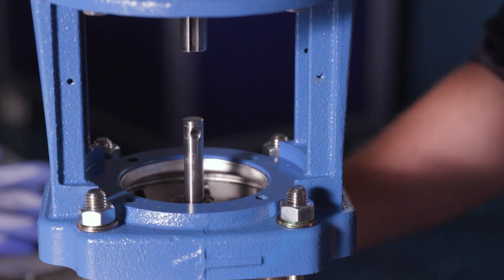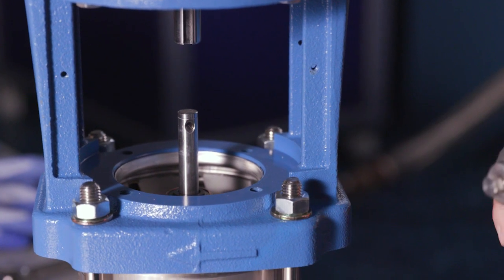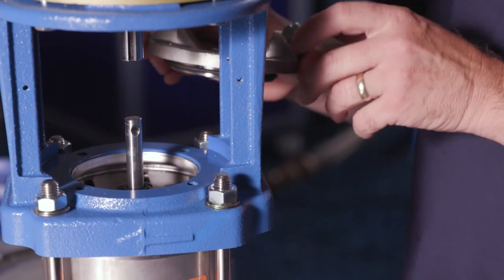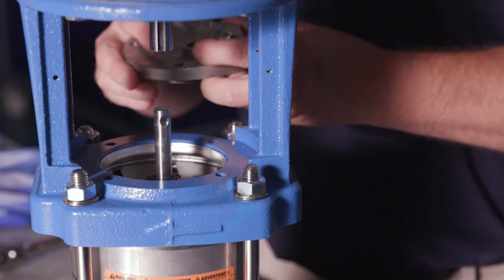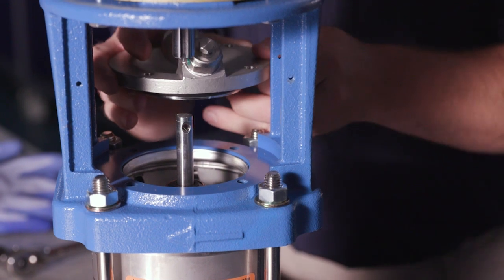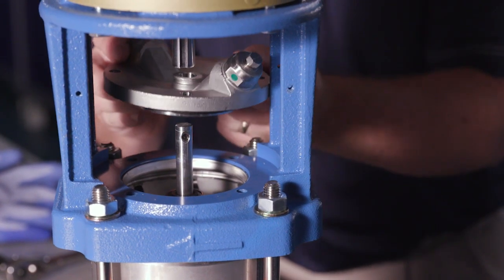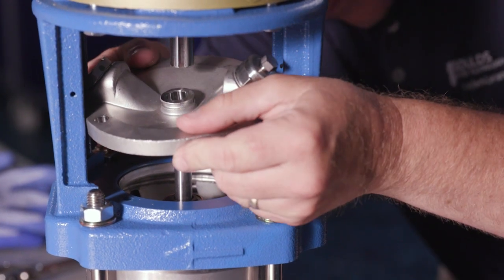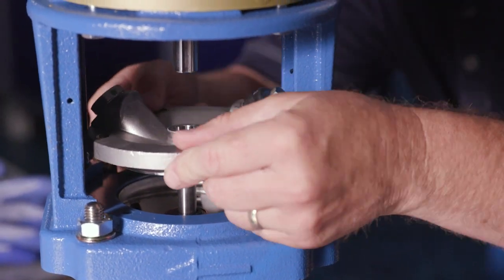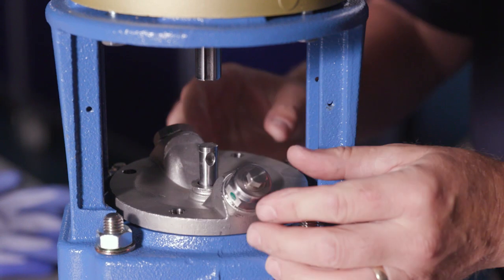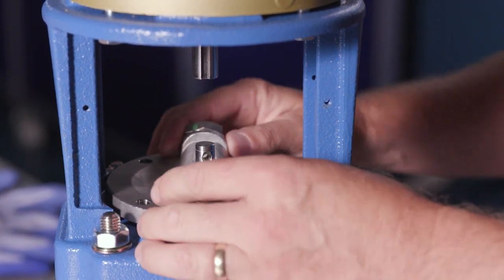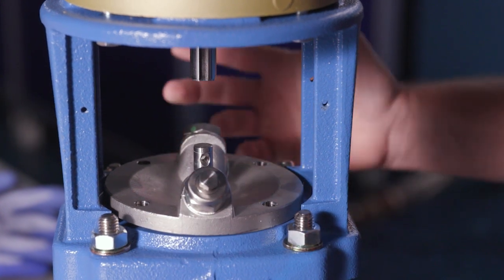Next, we want to take our seal plate and we want to carefully position that over the shaft, making sure that we don't chip that seal. Take your time on that and don't rush it. Make sure that we don't chip that on the install, because a chip is going to mean that it's going to leak.